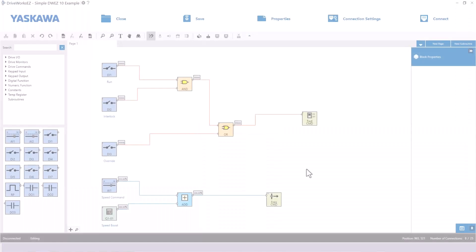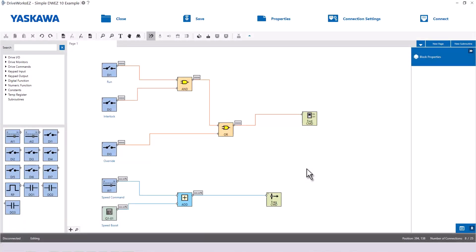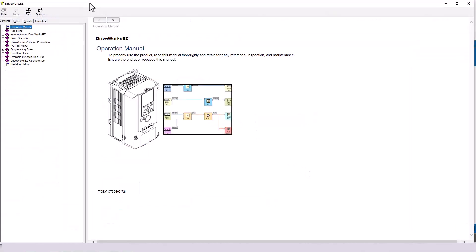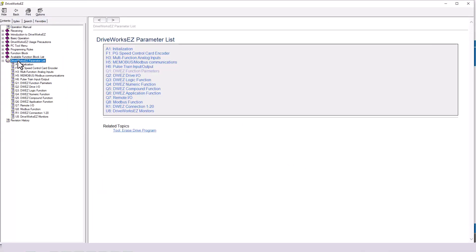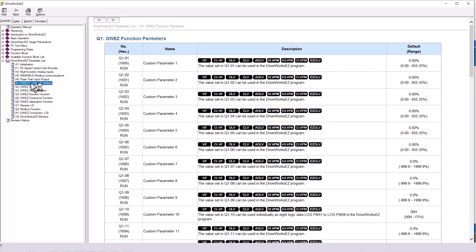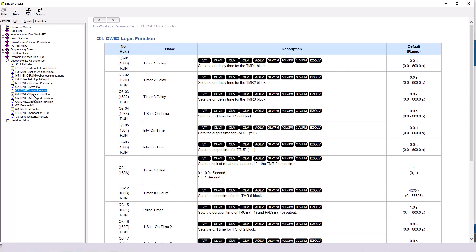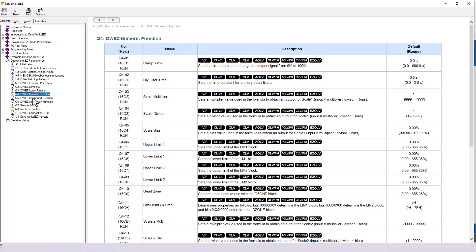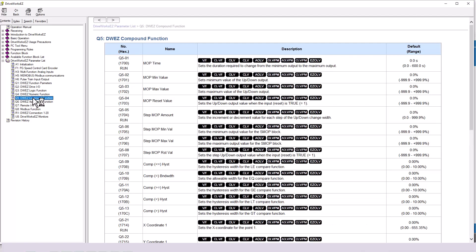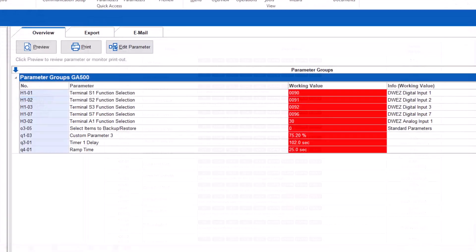While we are on the topic of parameters, the Q parameters in the drive are reserved for DriveWorks EZ. When you have a DriveWorks EZ program written to a drive, you will see the Modify Parameters menu will list Q parameters that are no longer at their factory default.